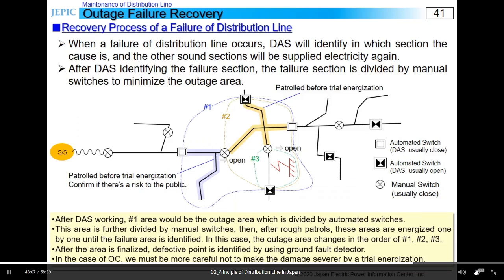Next, I'd like to explain briefly about the recovery procedure of a failure. When an outage failure occurs, how quickly we can recover is an important factor to improve SAIFI and SAIDI. Once a failure occurs, the distribution automation system will identify the defective section and the other sound sections will be energized automatically. After identifying the defective section, we further divide it into some sections by manual switches to clarify where the fault is. I'll explain a little more concretely with this illustration.